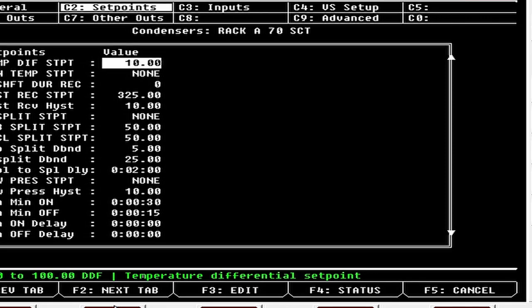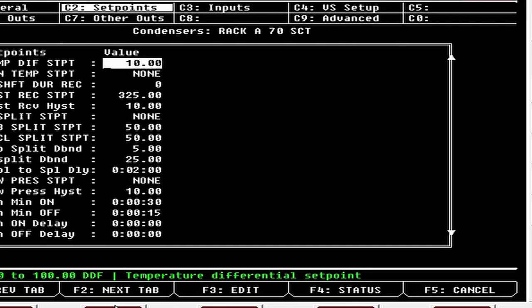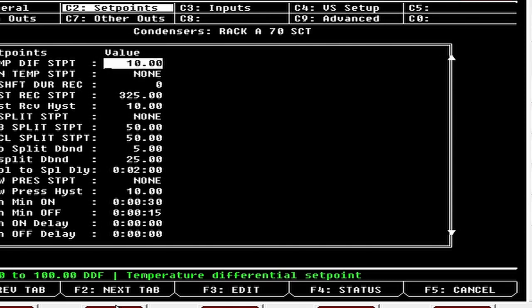If we go to the next tab it's our Set Points. Temp Differential Set Point is your TD on your condenser — whatever the legend and manufacturer say. Keep in mind the TD is kind of a made-up number; the design spec is usually way lower than reality, often closer to 7 or 8 degrees when they say 10. These condensers are oversized and when the load changes the TD changes. I generally don't like to set mine at 15 for medium temp; I usually go 12, though 10 and 10 or 10 and 12 are general targets for medium/low.